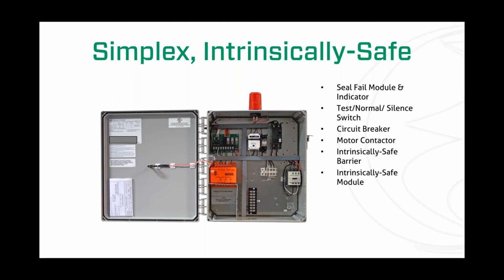Next is the motor contactor. Next, I'm going to point out the intrinsically safe barrier, which I spoke about earlier. It's very important. You'll want to run a conduit in on the inside of that barrier for your low voltage wires, and a conduit on the other side for your high voltage wires. I've had people come in who didn't understand what intrinsically safe barriers were for, and they took the screws out and threw it away. Don't do that. Learn what it's there for and keep it there. The next thing I'll point out is the intrinsically safe module itself.